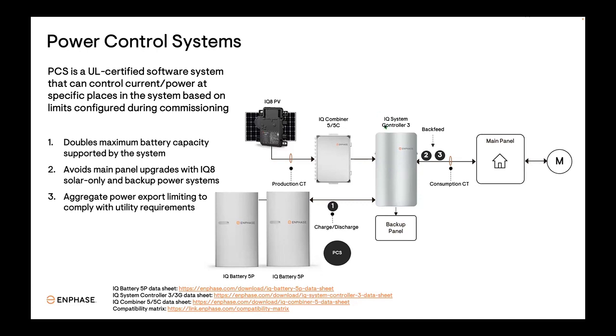discharging or producing power at the same time, especially during the daytime. The system is actually charging the batteries with excess PV, and only a portion of the current is backfeeding to the main panel. And then in the evening, the batteries may be backfeeding to the main panel. However, the solar system is not producing much power at that time.